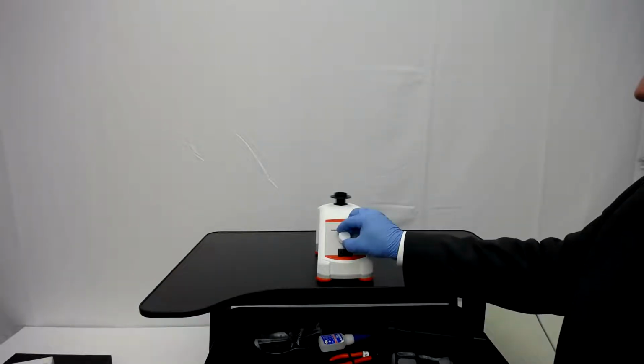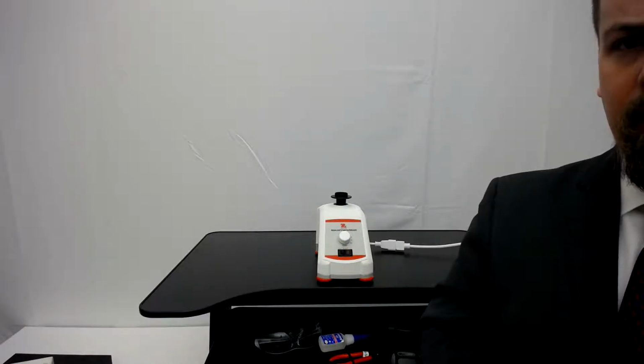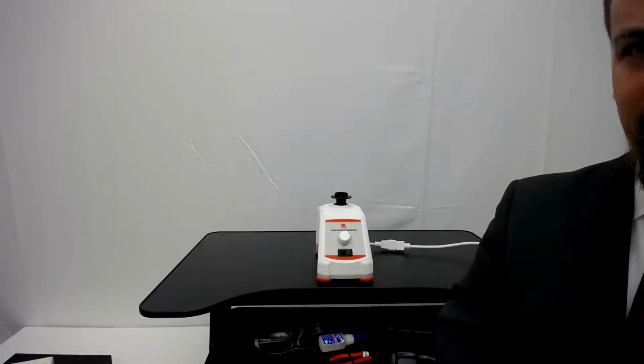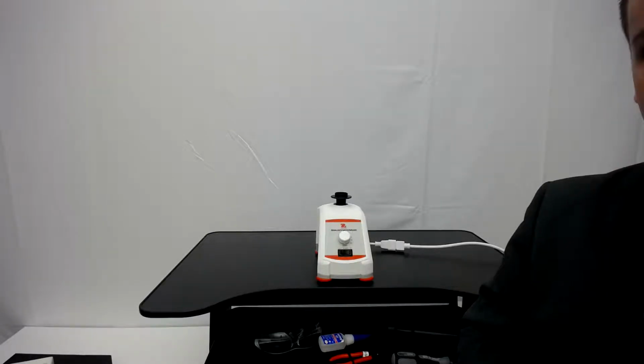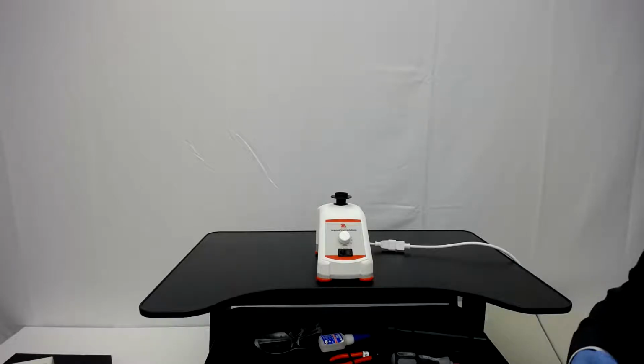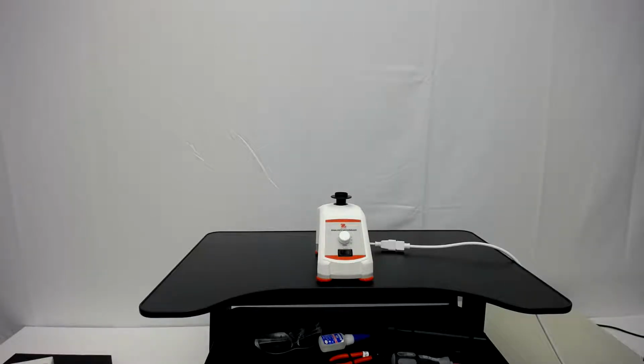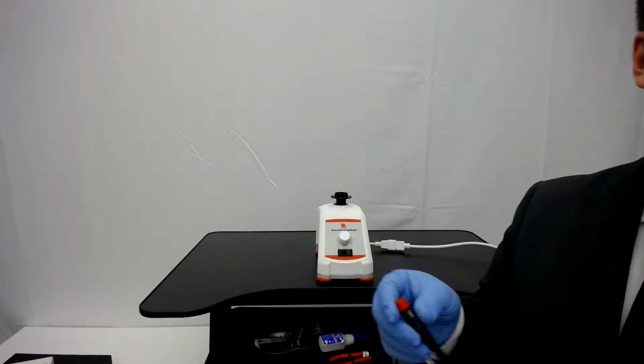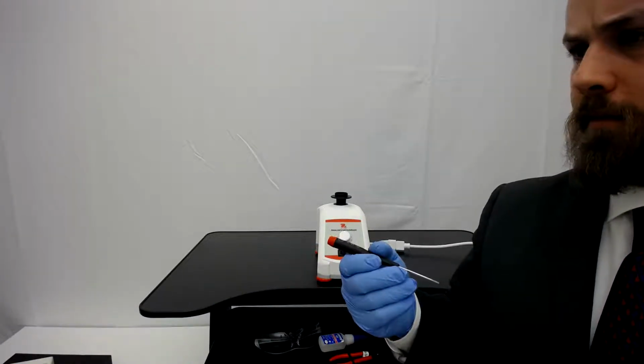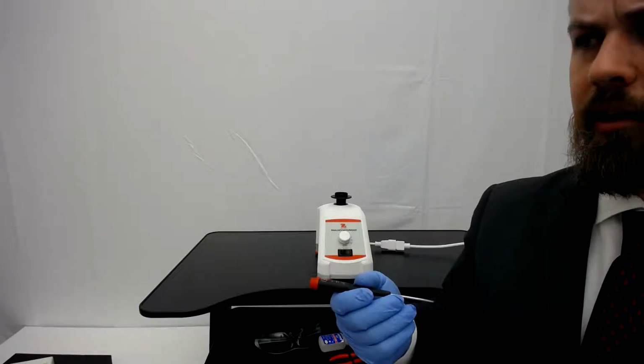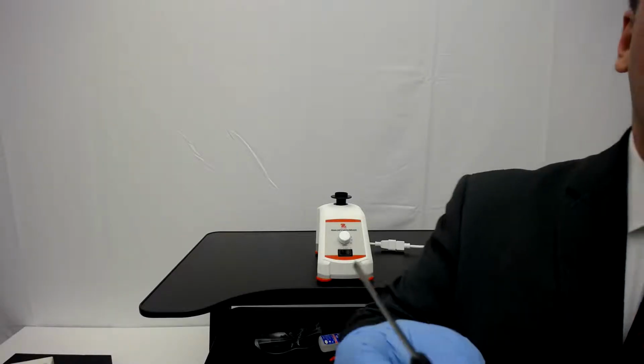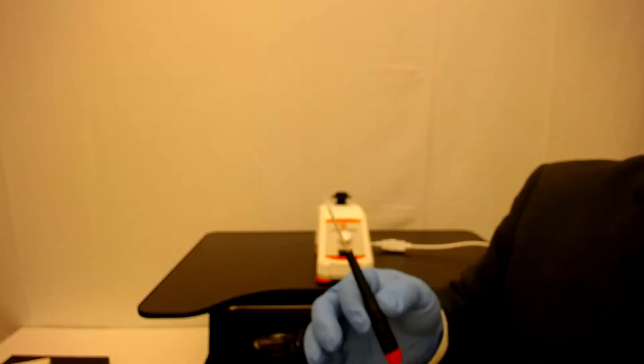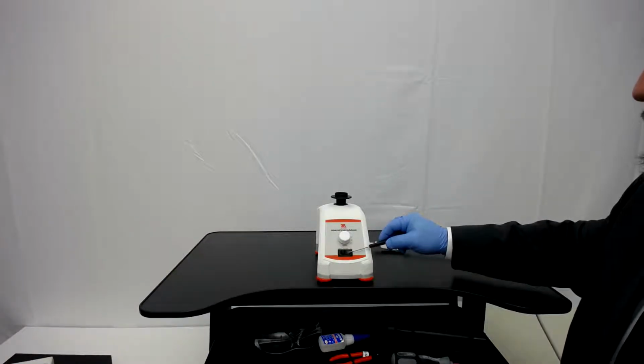Again, as with the mini hot plate, mini stirrers, the voltage regulation can be a little bit touchy. So make sure that you are running the unit from a specified voltage source. In this case, this is a 120 volt unit, and it's running at 60 hertz. So the other thing we'll need, the difference between the tools needed for this one and the hot plate stirrer, we'll need a very small flathead screwdriver. Let's see if you could see that. Okay, small flathead screwdriver, and that's to remove the power switch here.